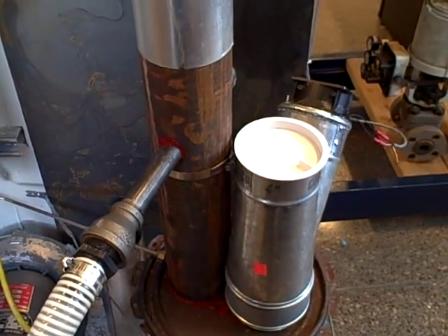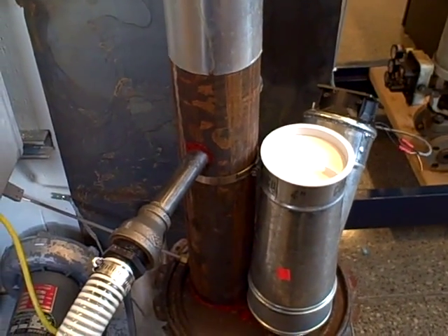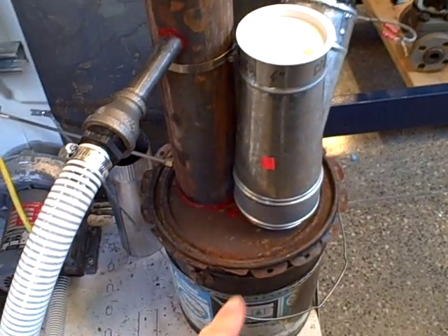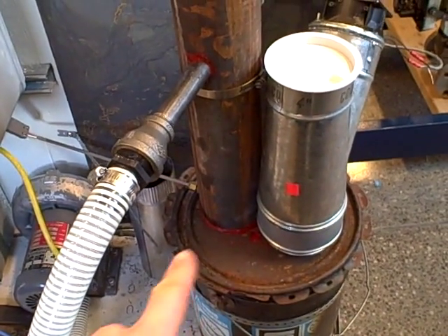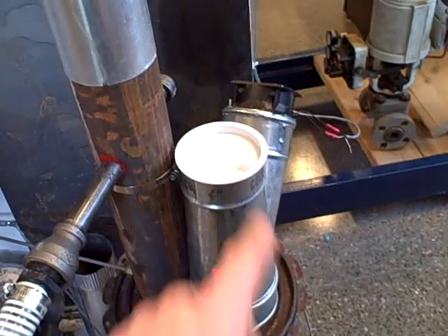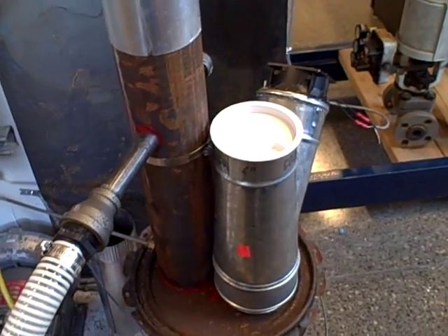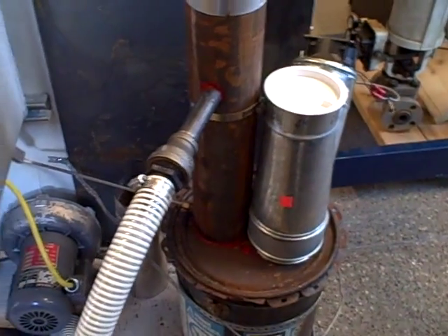The next phase after that, we're going to be adding cascade control. We will have a master PID algorithm in the PLC looking at temperature of the rocket stove. The output of that master controller is going to go to the set point of the slave controller, namely the airflow. So we'll have a cascade system, temperature cascading to airflow. And that'll be the next phase of development on our system.